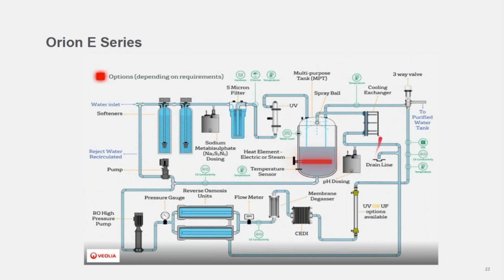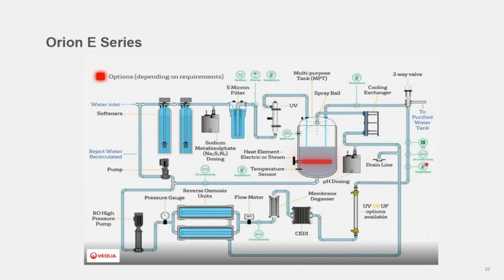So when the system is in optimum recycle mode, we don't throw any water down the drain, and we recover all of it, and we manage the temperature using the cooling exchanger. And during this recycle phase, also the conductivity is continuously measured, so we're not out of spec. So should the purified water call for any water, and there is demand, then we're within specification to fill the tank. So this manages any water being thrown down the drain for an 8-hour period during recycle.